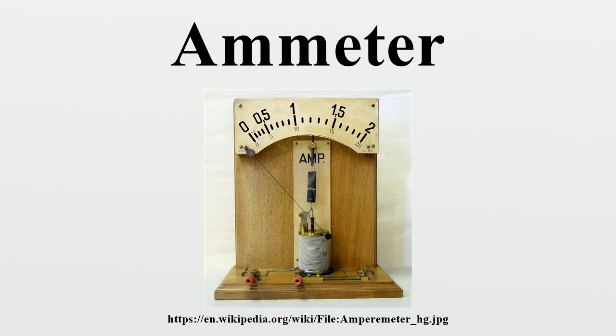Zero-center ammeters are used for applications requiring current to be measured with both polarities, common in scientific and industrial equipment. Zero-center ammeters are also commonly placed in series with a battery. In this application, the charging of the battery deflects the needle to one side of the scale and the discharging of the battery deflects the needle to the other side. A special type of zero-center ammeter for testing high currents in cars and trucks has a pivoted bar magnet that moves the pointer, and a fixed bar magnet to keep the pointer centered with no current. The magnetic field around the wire carrying current to be measured deflects the moving magnet.